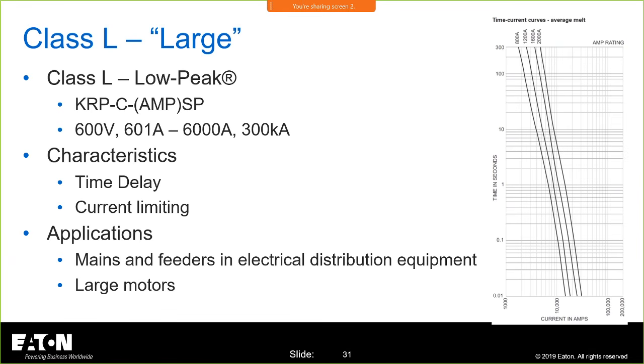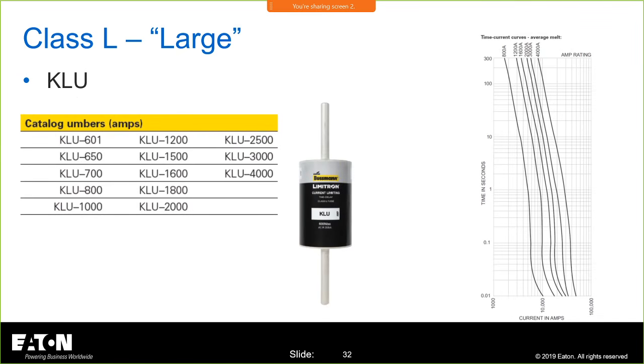Class L, again, those are the curves. So that's what your trip curve looks like. These are average melt curves. They don't have the bands on them, the plus or minus. These are just your average melt. And what I'm more interested to help you see is that you still have some distance here. You know, you have this arc, and it's not a fuse that looks like this, right? Okay, it has the arc that will get you through those motor inrush currents and things of that nature in transformers. So they have a little bit of time delay built into those, but still fast acting.